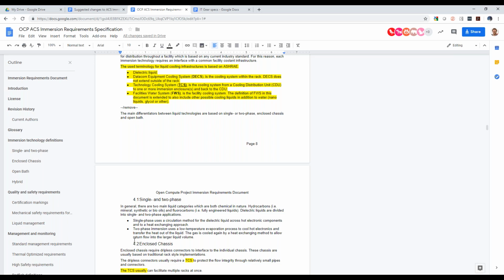Yeah, and that's where I'm afraid we're going to start entering into a limiting domain. It's not only limiting because of that, but if you have a single CDU, for instance with the GRC case, you'll have multiple baths, and you'd want to know the temperature in those baths - that would be the dielectric temperature, not the CDU temperature. So it's at the inflow of the bath, so you can determine it at the DECS level, is that what you're saying? I agree with that, but I also want to know it at the CDU level to make sure I know how much power I'm actually cooling through the CDU, and if I have any issues with that.